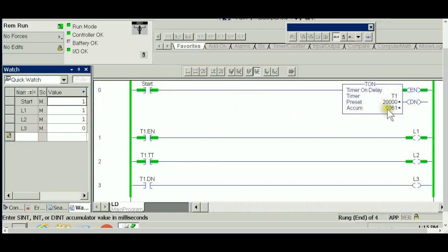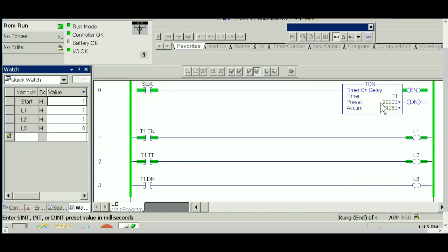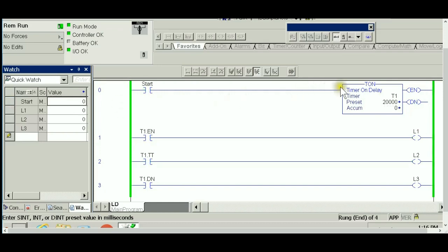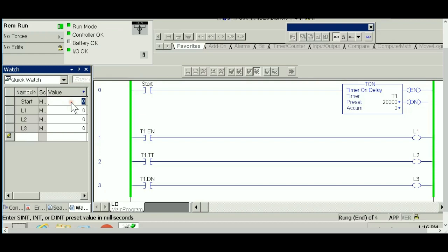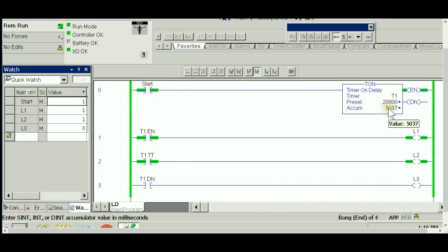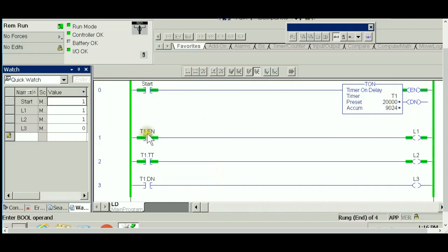It will start timing from accumulator equals zero, aiming for the accumulator to hit the preset value. This timer is non-retentive, meaning anytime the input to the timer goes to zero, this timer will reset. One more time, run the timer—the input is true, the timer is running, the accumulator is aiming to get the preset value.